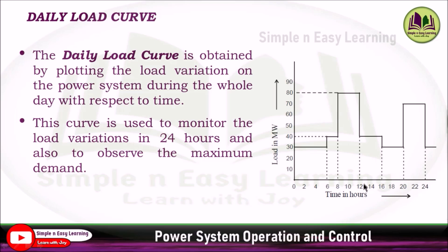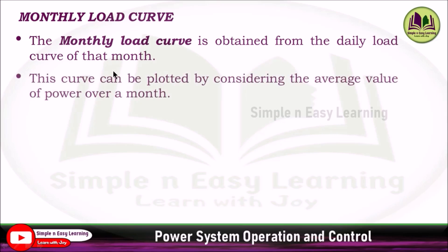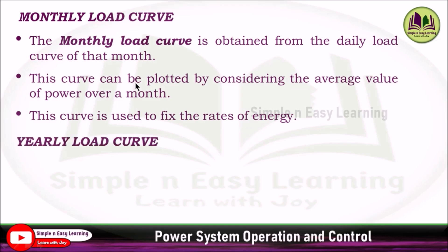For example, in this load curve we can observe that the maximum demand is 80 megawatt, which occurs during 8 AM to 12 noon. For the monthly load curve, it can be obtained from the daily load curve of that particular month by considering the average value of power over a month — that is, 30 days. This curve is used to fix the rates of energy for a particular month based on how much energy is consumed.